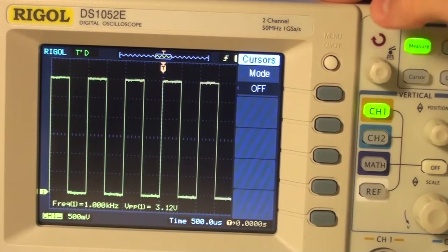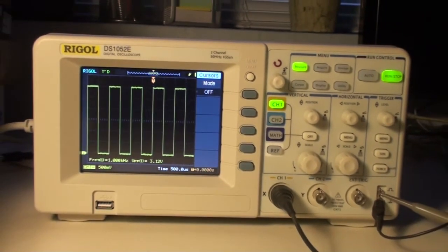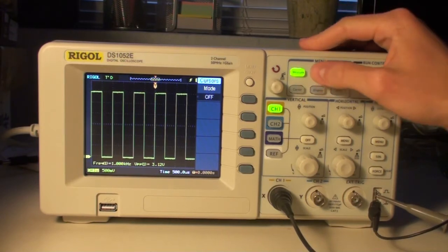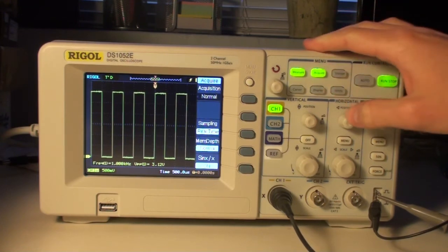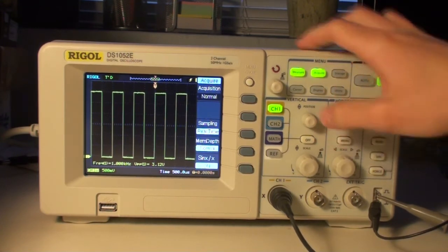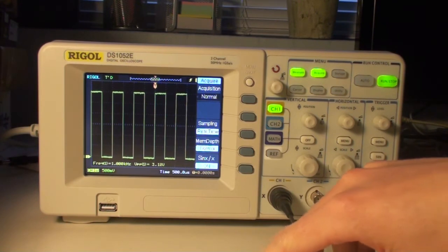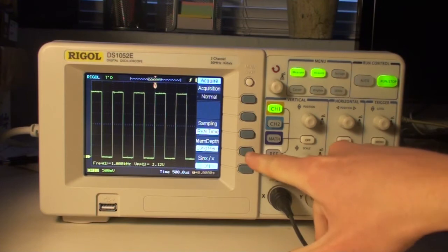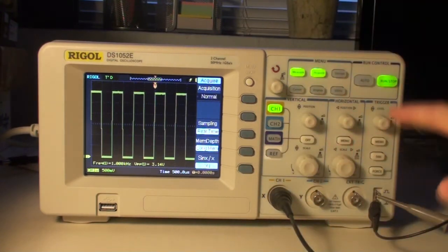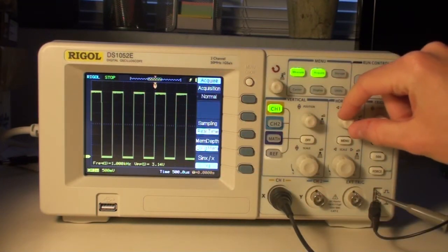Okay, let's disable the cursor and then let's have a look at the Acquire function. The Acquire function up here enables us to do different samplings. We can change the sample depth, the memory depth, of how many samples are acquired and stored into the internal RAM. This is great if you're looking at big waves, big samples. You can set the memory depth to large, long, and then you can stop, for example, and then you can start viewing this by moving the position slider.